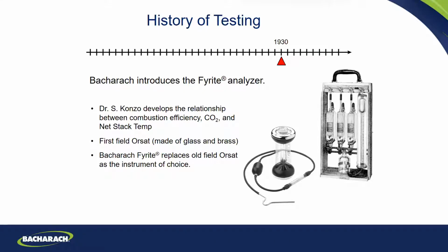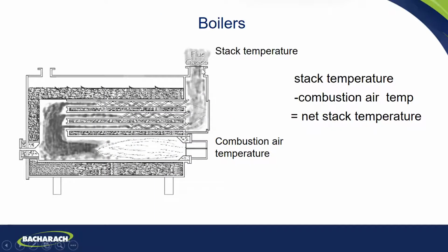In 1928, Dr. Konzo came up with a formula. If we took a stack temperature at the breeching, where the stack meets the boiler, let's say it's 480 degrees, and we minus the air going into that boiler, since we didn't heat that combustion air. If that was 80 degrees going in, we subtract 80 from 480, giving us 400 degrees net stack temperature.